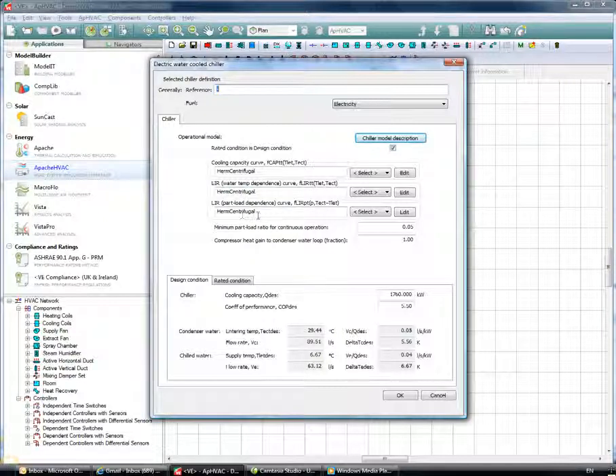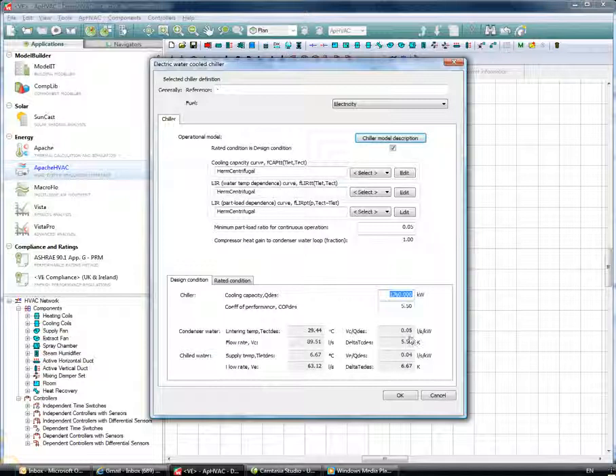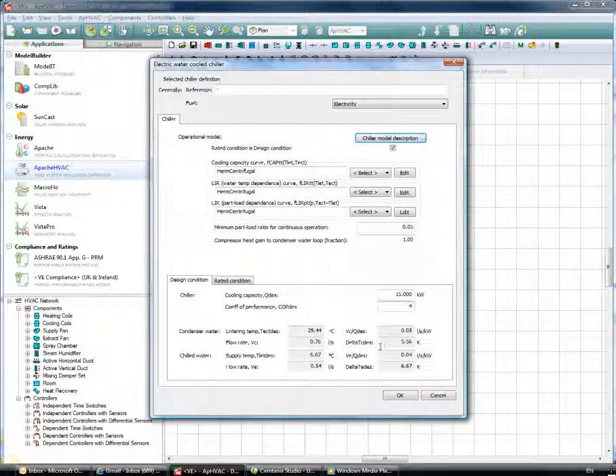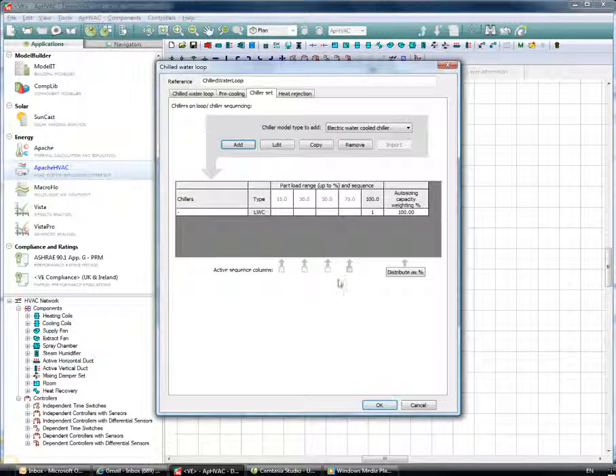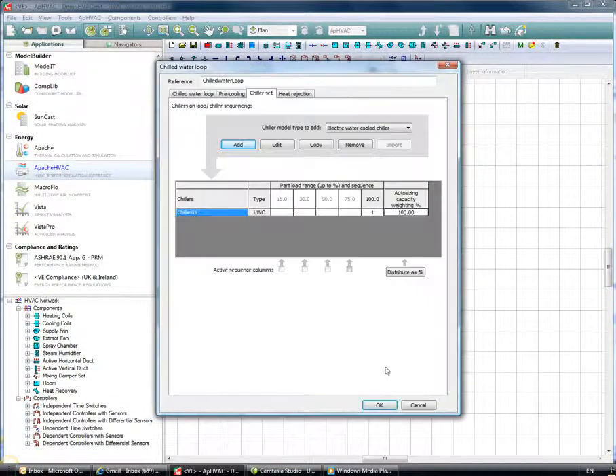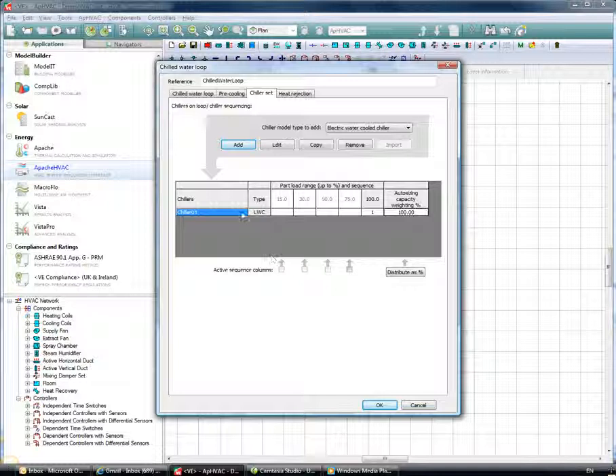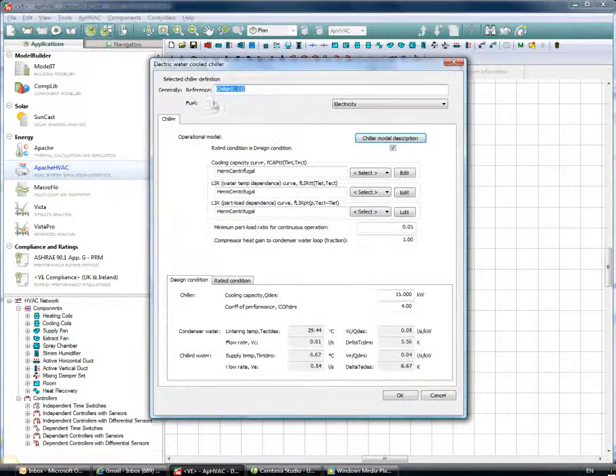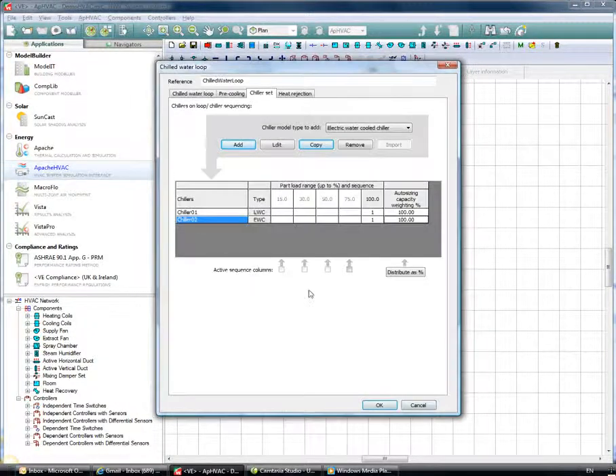In the electric water-cooled chiller section, I can select the cooling capacity curve, the water temperature dependence curve, and the part load dependence curves. I'll set the chiller capacity to 15 and the COP to 4. Clicking OK, the chiller is in place — I'll name it 'Chiller 01'. We can also sequence chillers: I'll copy the existing chiller, rename it 'Chiller 02', keep the same capacity and COP, and sequence them so one has priority over the other.